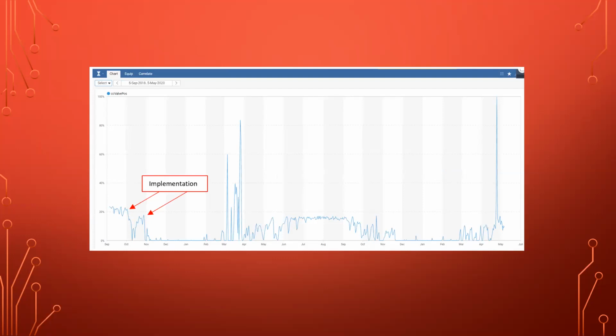This slide is an example of really what we want to see out of every air handler. This is an air handler we retro-commissioned in October 2018. We've now established a new baseline for this air handler with new sequencing. This is exactly what we want to see - no chilled water consumption during the winter, and it doesn't even get above 20% of the valve being open, even in the summertime. I think we're able to really accomplish having every air handler look like this by using this constant monitoring process with the analytics software.